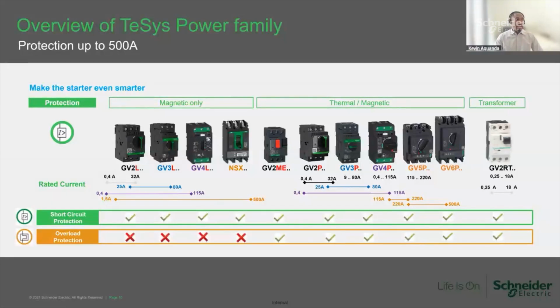So just diving into the different functions that we have. From TeSys Power with the protection breakers, this is a very wide portfolio, covering multiple applications, and they come in different varieties. For TeSys Power, which is our GV range of motor protection breakers, within the portfolio we have either magnetic only solutions, used in 3 product configurations where you would install a separate overload for protection of the motor. We have thermal magnetic solutions that provide a more compact option, where the single device will perform both short circuit and overload protection, hence allowing for use of a 2 product configuration for your motor starter. And then we also have a transformer protection option in the GV2RT.